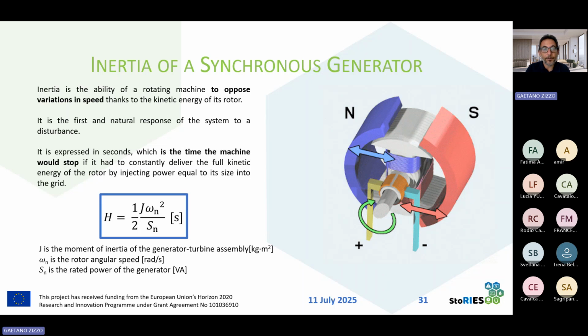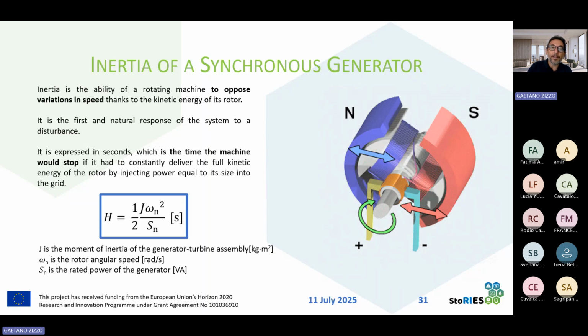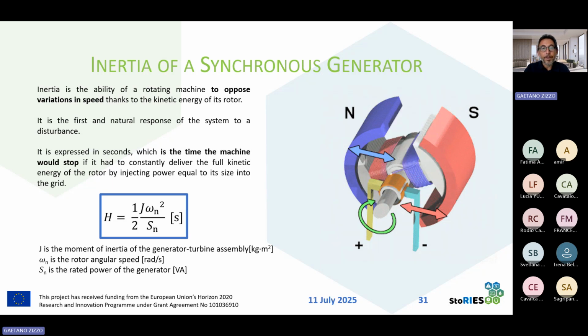But what is the inertia of a system? The inertia is the ability of a rotating machine to oppose variation in speed thanks to the kinetic energy of its rotor. So it's the first and natural response of the generator to a disturbance, and is usually expressed in seconds, that is the time that the machine will run if it had to constantly deliver the full kinetic energy of the rotor by injecting power equal to its size into the grid. So this is the formula for calculating the inertia of a rotating generator.